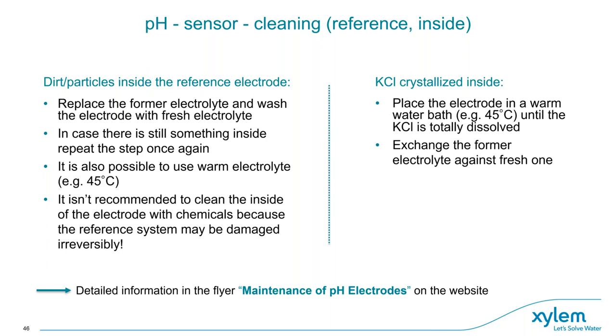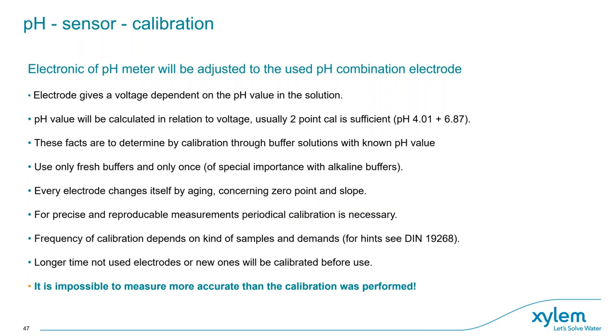The zero point and slope of pH sensors change over time, so regular adjustment is required. What is commonly called calibration is really a relative adjustment of the pH meter to the actual slope and zero point of the used electrode. The most common is a two-point calibration with two buffers, for example pH 4 and pH 7. Multi-point calibration is also possible. It is very important to use only fresh buffers and only once. The frequency of calibration depends on the kind of samples and individual demands — a standard might be weekly, but some operators calibrate twice a day. Remember: it is impossible to measure more accurately than the calibration was performed.